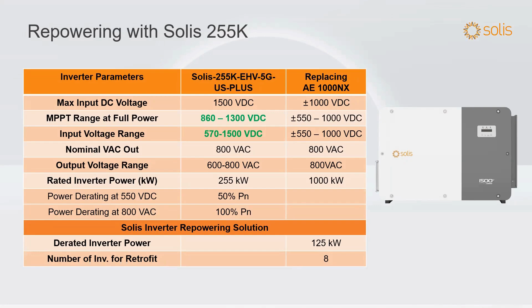So these wide operating ranges are useful. You can see that if you're kind of way outside the input voltage range - let's say power derating at 550 volts, very low - you can still pull 50% out of the inverter. But should you get into the voltage range, especially something over 860, you can pull full power out. So it's a real nice way to replace those old inverters with a new solution that can give you optimal power output as well as good comms.